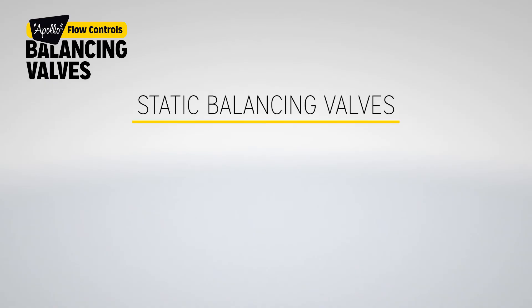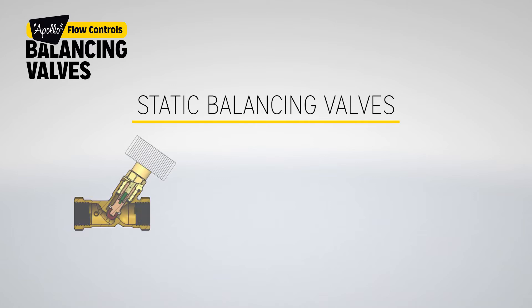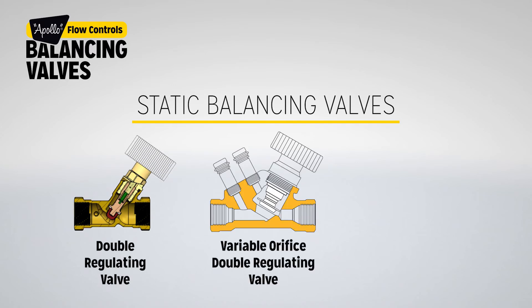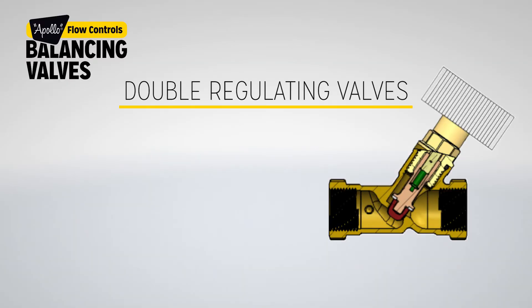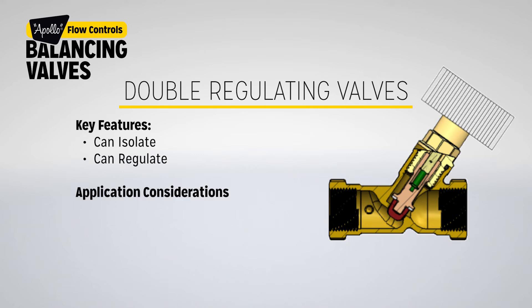The three main types of static balancing valves can be identified by different design styles: the double regulating valve, the variable orifice double regulating valve, and the fixed orifice double regulating valve. Double regulating valve key features: it can isolate and can regulate. Application consideration: the valve cannot measure flow.